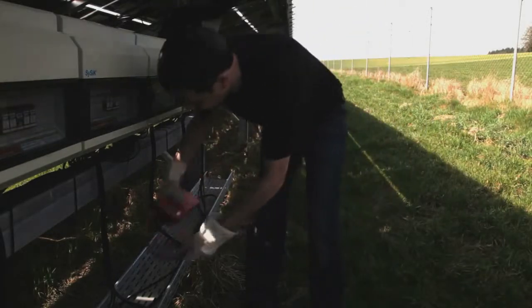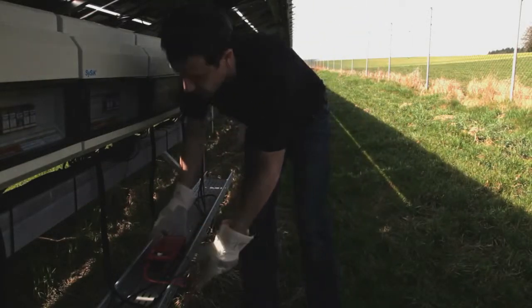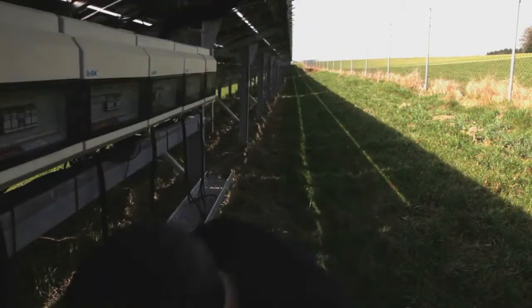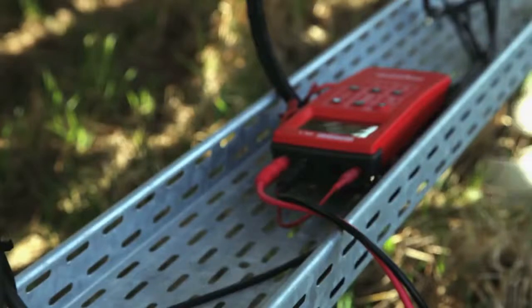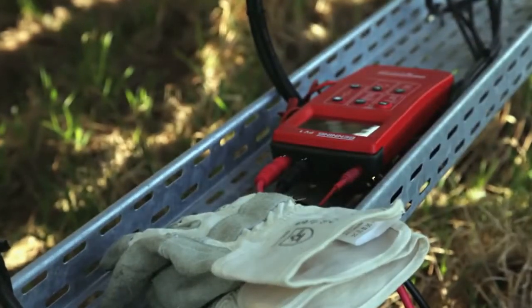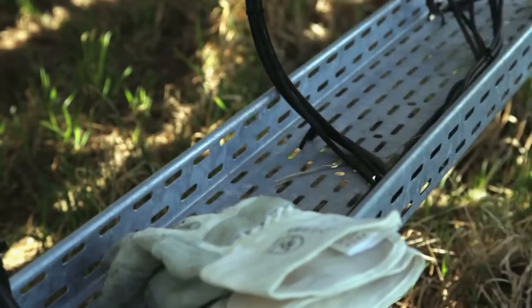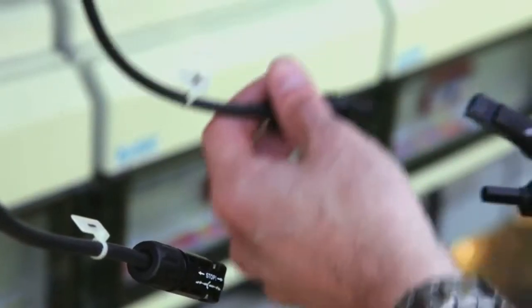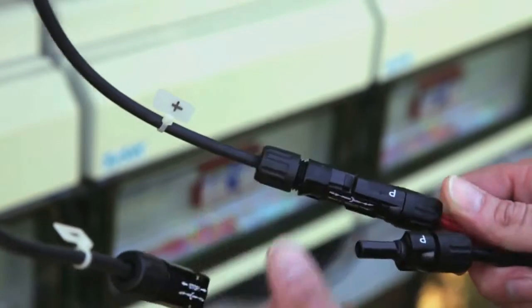Before starting measurements on the PV generator, disconnect the generator from the inverter. For this, open the DC isolator switch and disconnect the PV string cable from the inverter. Connect the red measuring line to the earthed module frame and connect the PV string cable to the enclosed MC4 or SunClicks test cables.